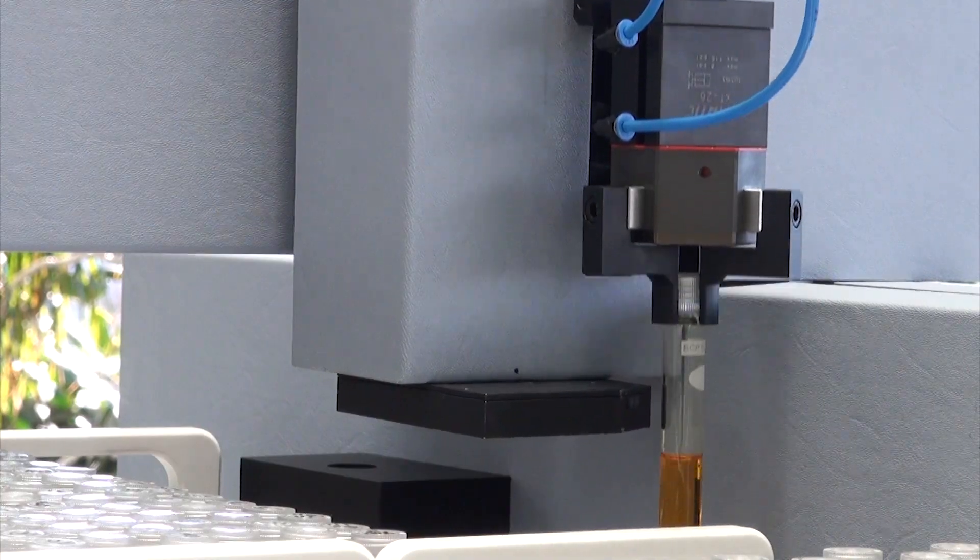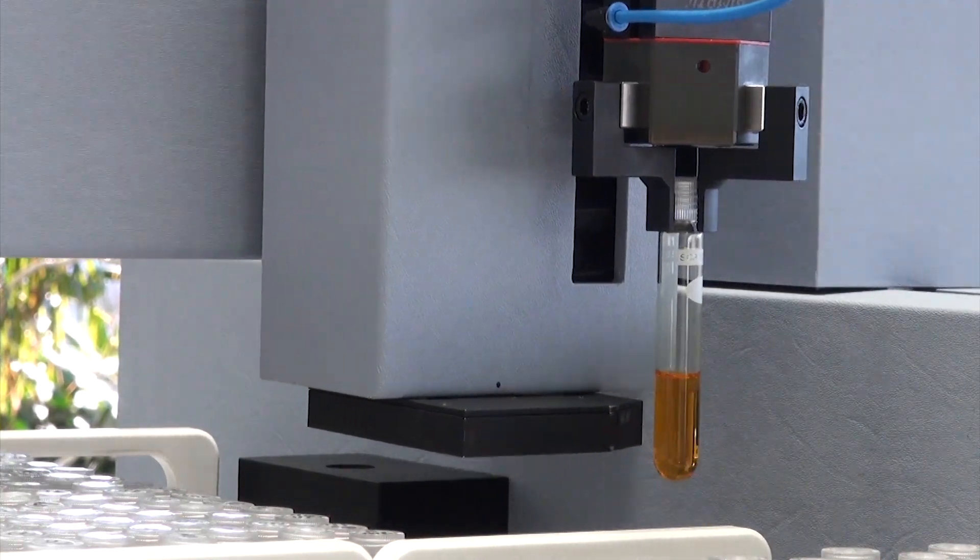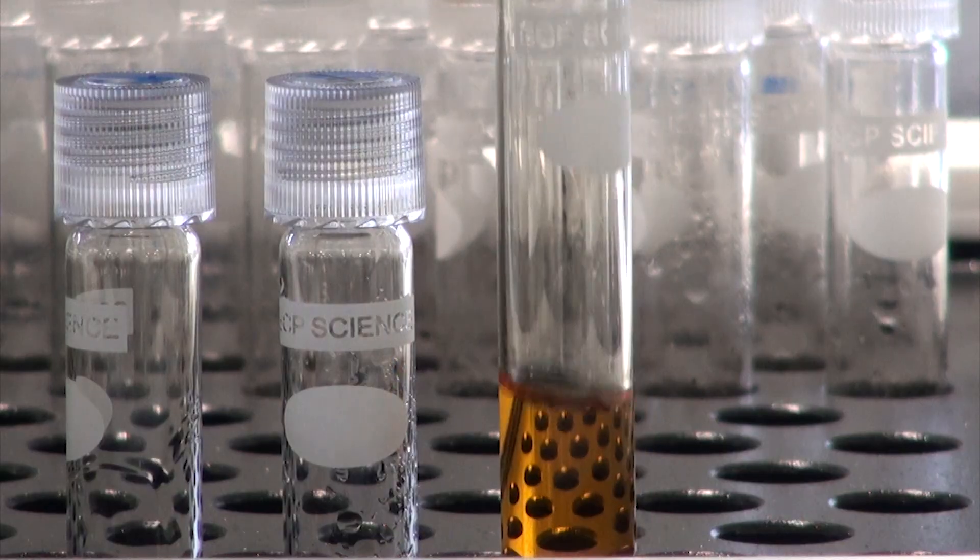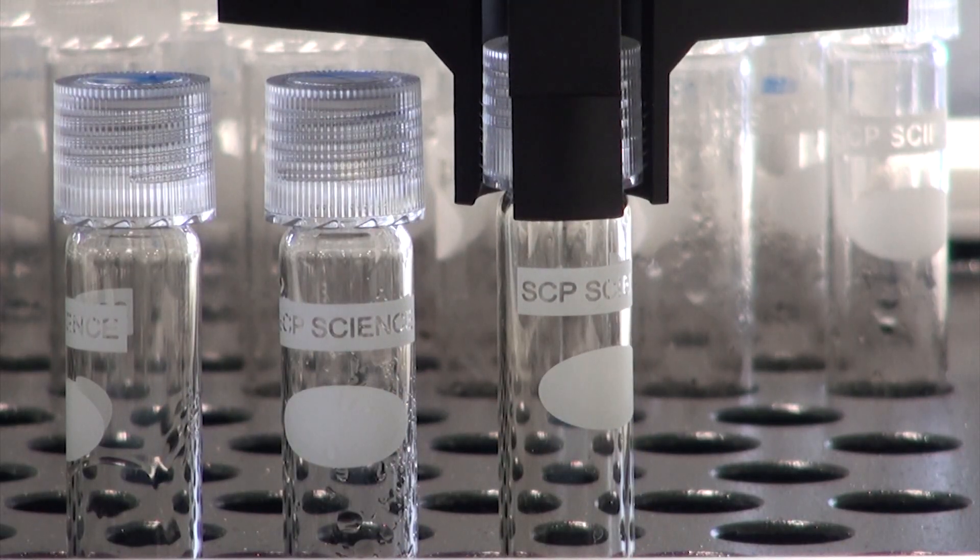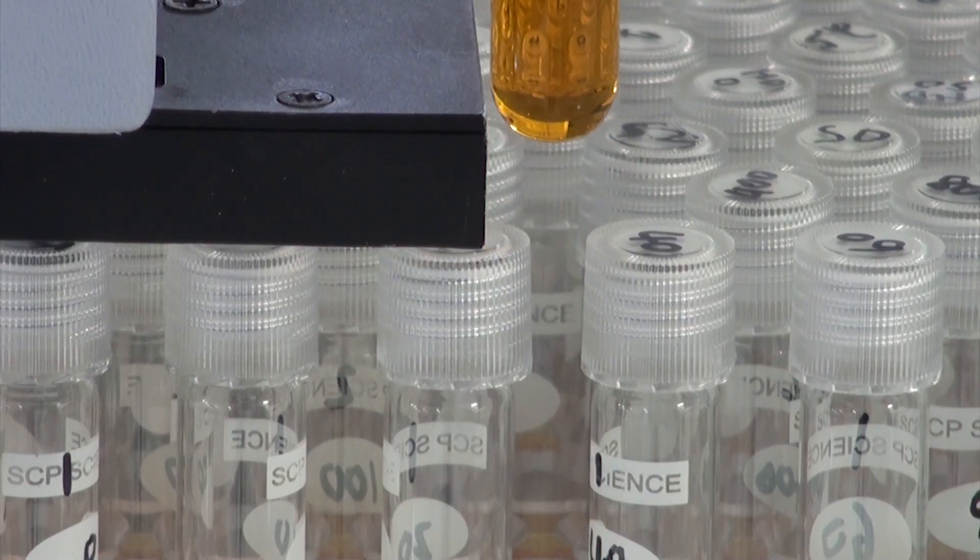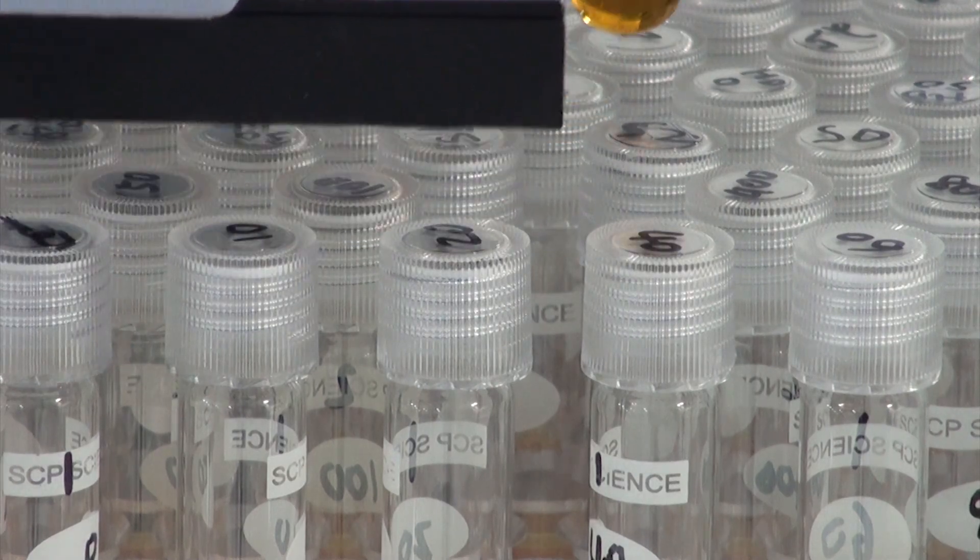EasyPrep COD 200 uses an XYZ robot with stepper motors and timing belts. Samples are moved with the use of an air-assisted gripper. The chemist can select the speed and amplitude of mixing movement and when the sample is mixed.